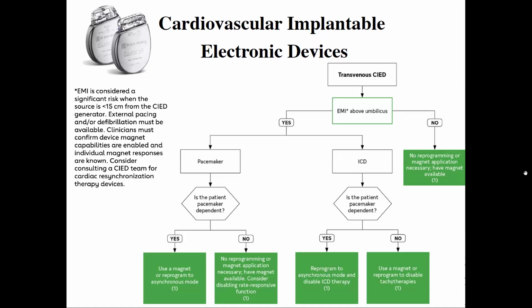So if there's going to be continuous cautery on a big lesion in the liver, and the patient's dependent, that patient should be reprogrammed preoperatively. If the surgeon is going to give you EMI. If the surgeon says, I can use bipolar, you don't have to worry. Because bipolar is current between the two ends of the instrument and it does not cause EMI. Or if the surgeon can do short bursts of cautery, you do not have to worry because they'll only lose their heartbeat for short periods of time.